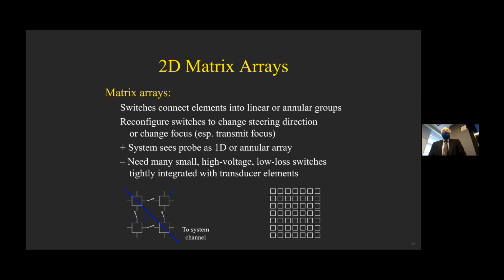If I talk about how you then manage an individual 2D transducer array, I can think of doing that in essentially two different ways. The first way is what I'm going to call this 2D matrix array, where you use a bunch of switches in the array to connect different groups of elements together. And by reconfiguring the way those switches are, you're able to change how the beamforming is done. So it's essentially converting that two-dimensional array into a one-dimensional array for the purposes of beamforming.